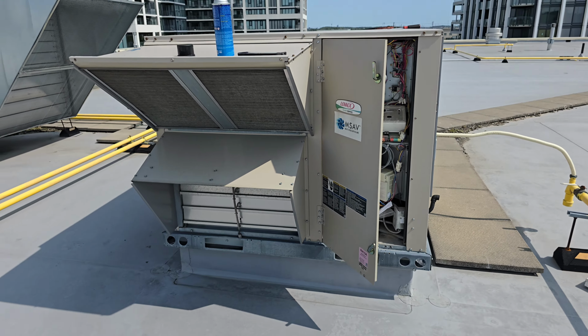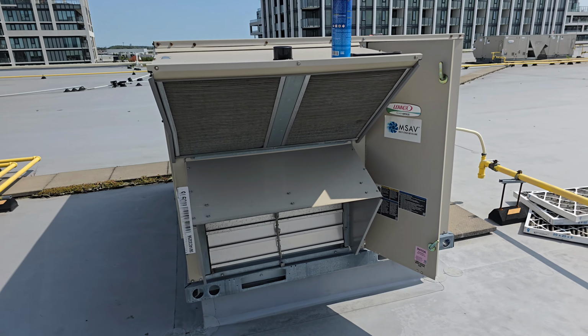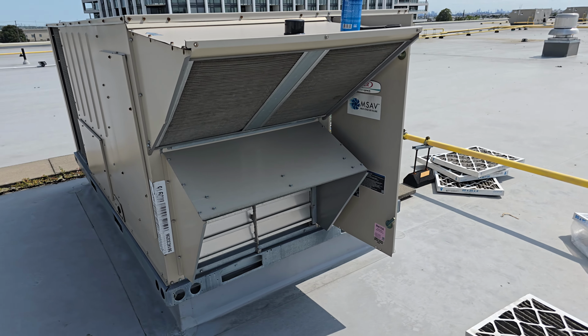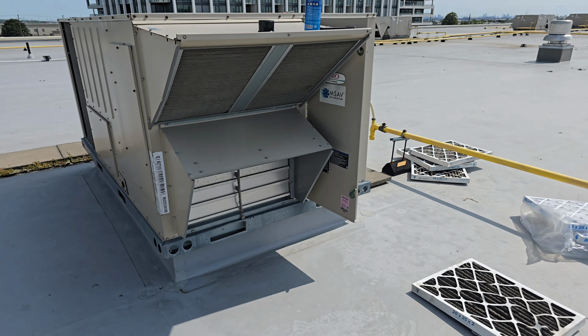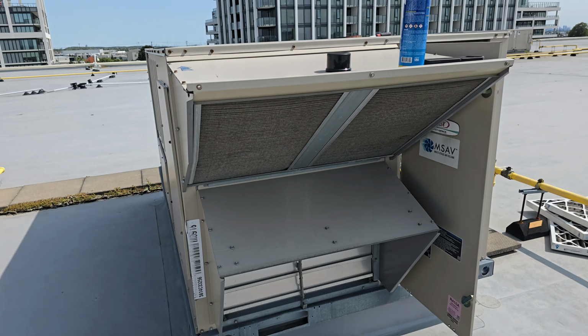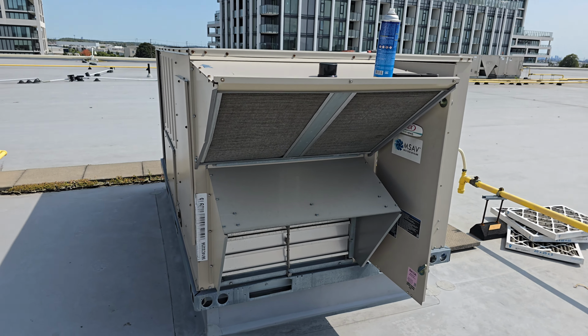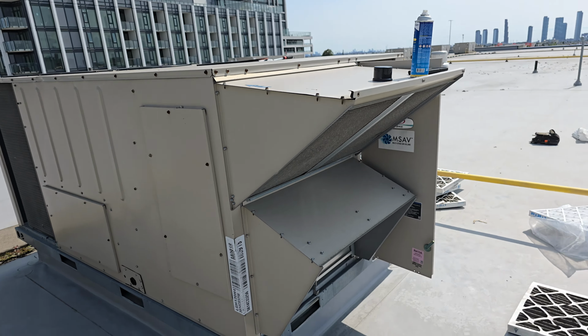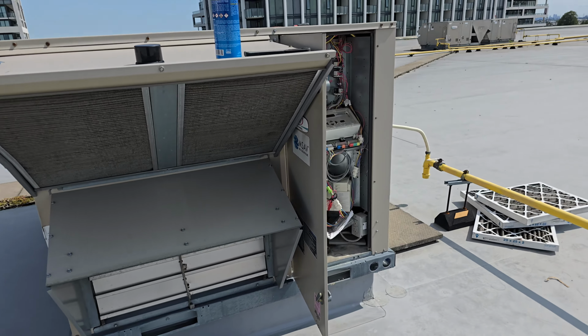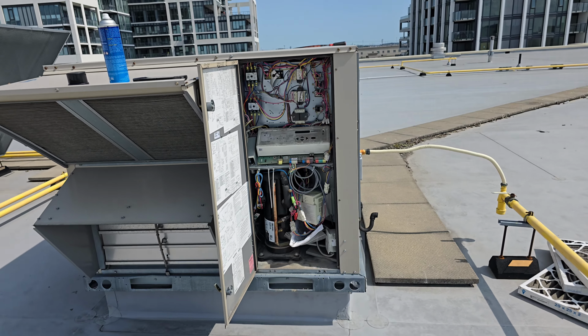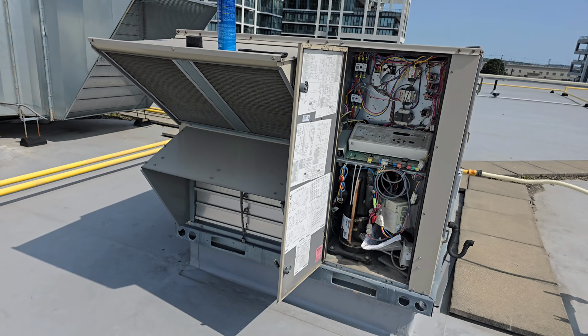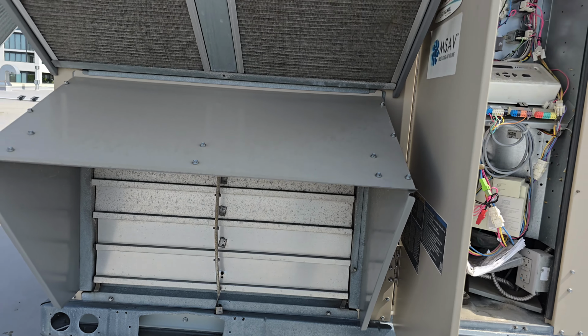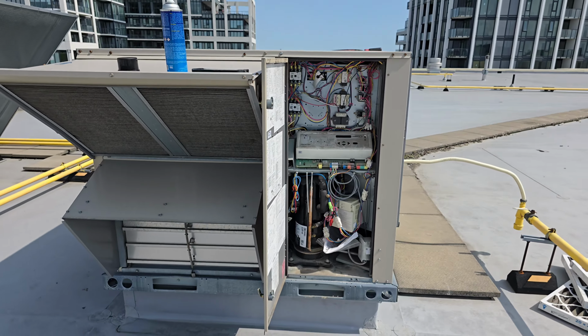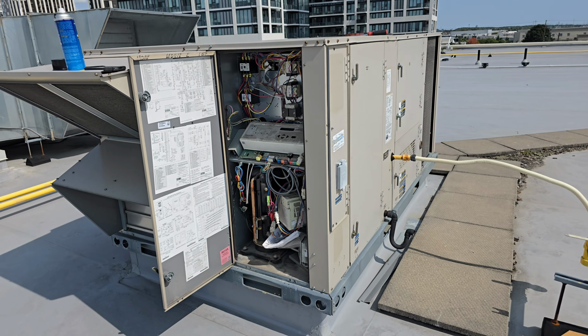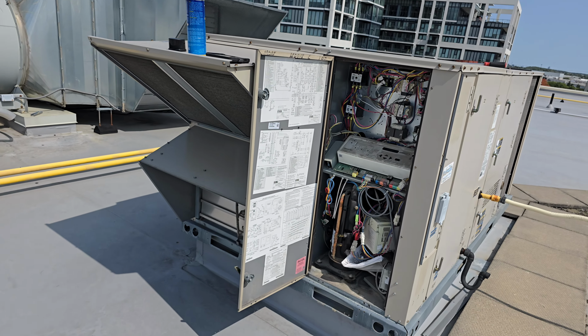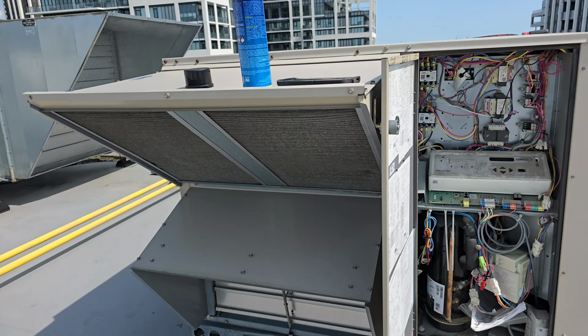So this unit does have an economizer. The function of the economizer is, say in springtime, when it's really cold outside and indoor could be very warm, instead of the AC kicking in, the economizer is going to sense it and say, oh, I'm going to give you free cooling. It's just going to open up this damper and allow fresh air to come in, and when the room is satisfied, then it will cut it off. So that's the economizer. So make sure you check your linkages to make sure they are free and nothing is hanging on them, and clean the air filter as well.